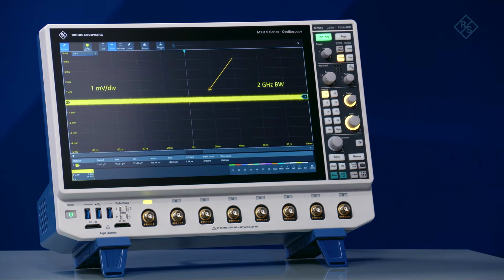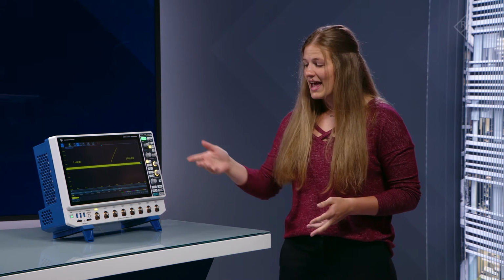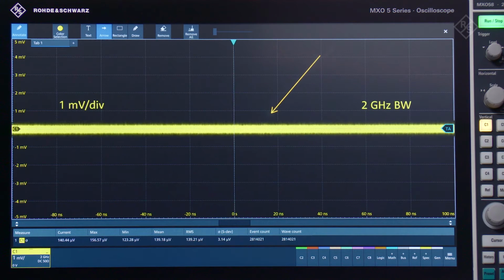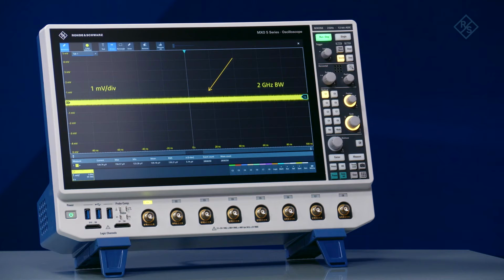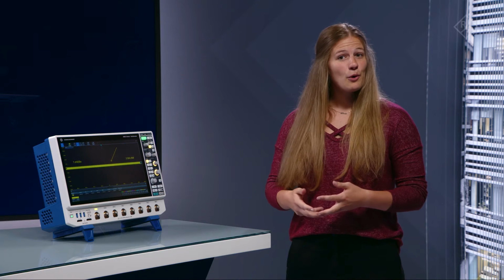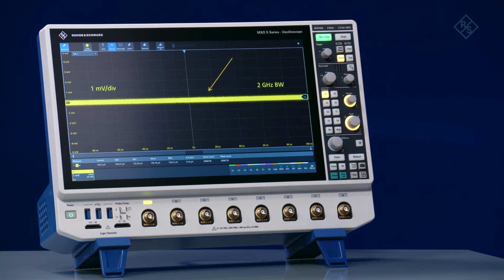Let's take a look. Users often care about noise at the most sensitive vertical settings, and the MXO 5 scope has the lowest noise floor in its class at 1 millivolt per division. Observe the standard deviation of the noise, about 140 microvolts at this particular setting. This is important because a scope can never measure a signal that is lower than its own noise floor. By using a low noise scope like the MXO 5, all automated measurement values will be more accurate, ensuring precise results.